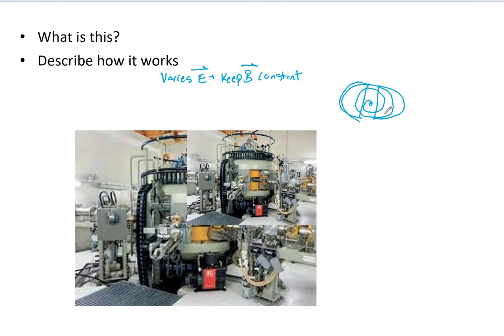So typically from these cyclotrons, these are mono-energetic, meaning you're only going to get one energy, and it's going to be a continuous beam. Typically these things are 3.5 to 5 MeV.